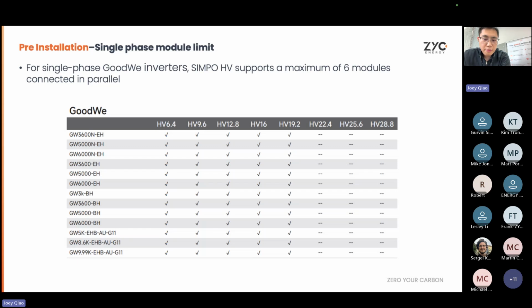The GoodWe single phase and 3 phase have different voltages, and to match the inverter voltage, our battery voltage is also different. So the minimum and maximum number of modules required for single phase and 3 phase is different. Here in the pictures, this is all single phase. If you have the single phase GoodWe, make sure on the battery, our SIMPO HV, the maximum battery module per stack is 6 modules, from the minimum 6.4 (2 modules) up to 3, 4, 5, 6 - it's all compatible. But please don't use 7, 8, or even 9 batteries in 1 stack to pair with the GoodWe single phase, it's not compatible. So just make sure to pick the correct number of batteries per stack.